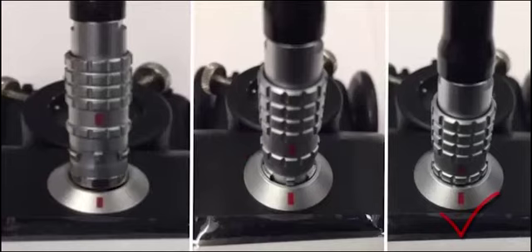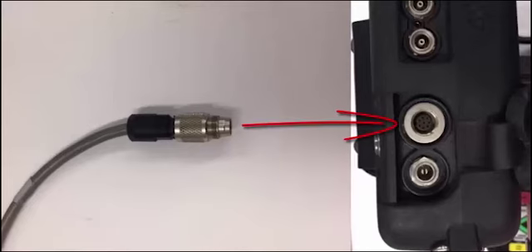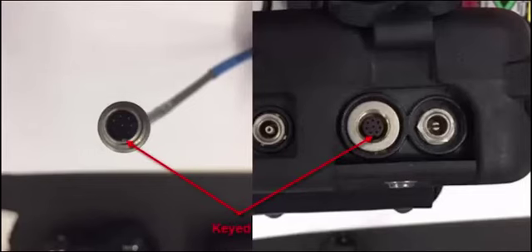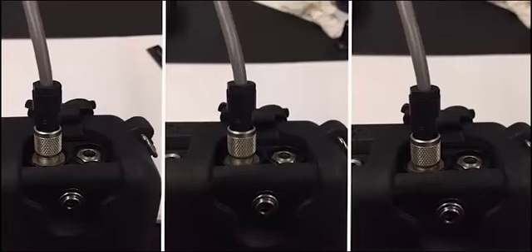We can now plug the other end of the encoder cable into the top of the 38DL Plus. These connectors are also keyed, but they do not contain red markers. Pay close attention when connecting the encoder cable to the top of the 38DL Plus. Make sure that the keyed section of the encoder cable is properly seated in the slot of the port on the top of the 38DL Plus.